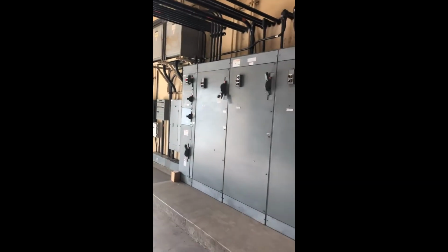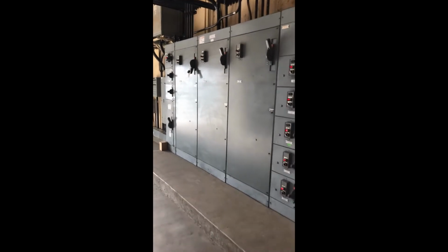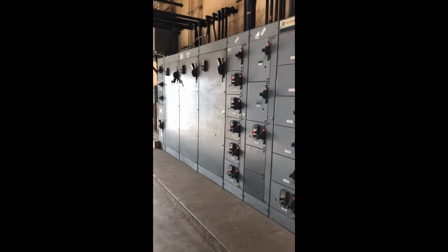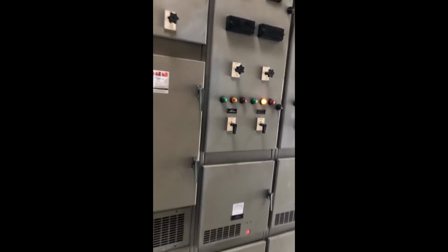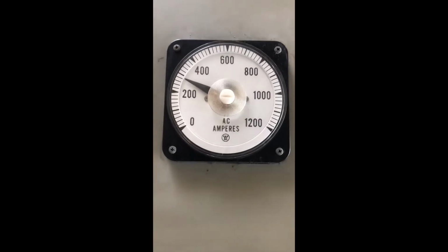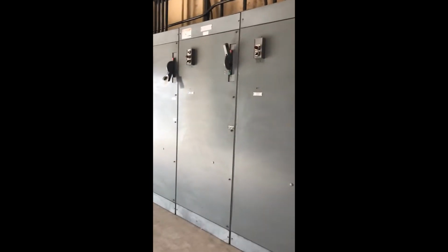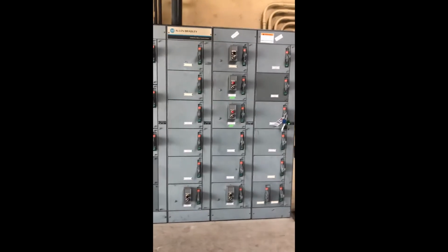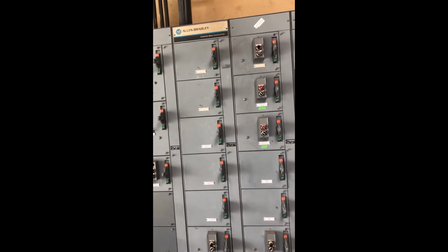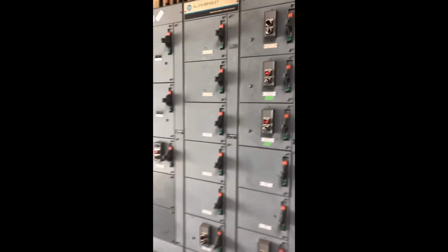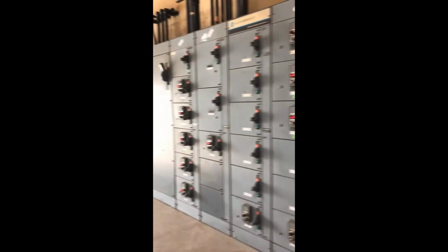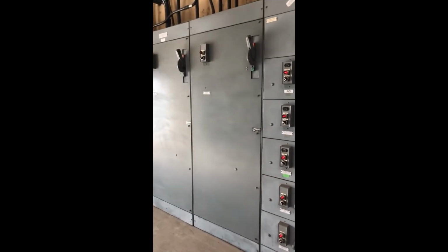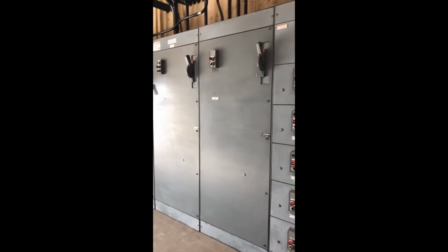And behind me is a relatively large one. This is MCC-D. MCC-D should have the most load right now. It drives our blowers. And here is D. And yeah, it's got a little bit of load on it. These are the smaller buckets. The buckets depend on the horsepower of the motor. You know, a smaller motor is going to have a smaller bucket. And you can see these ones are pretty big. These are the 250 horsepower blowers that we have here.